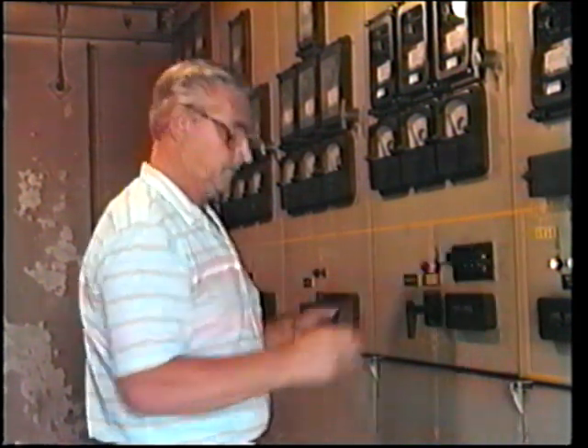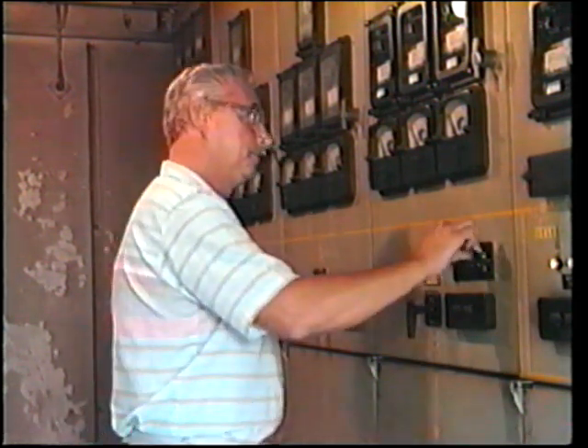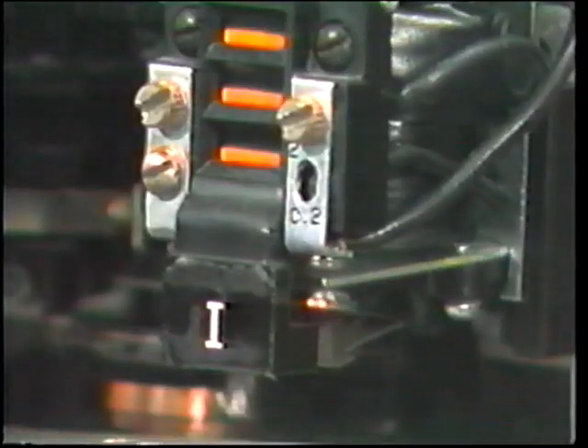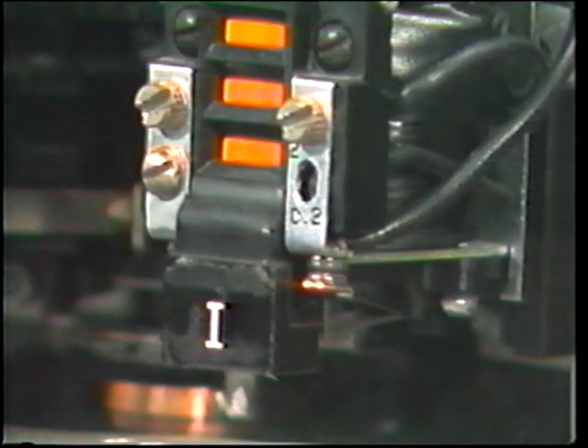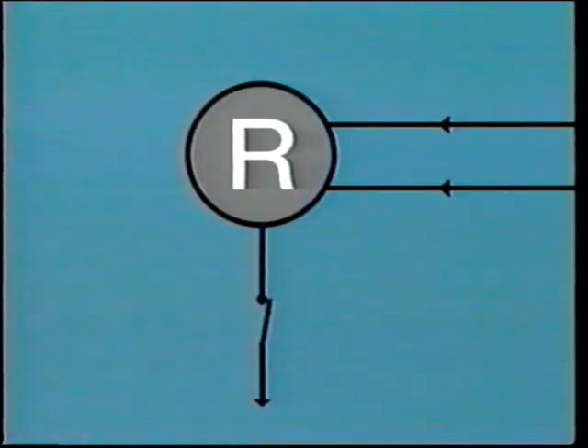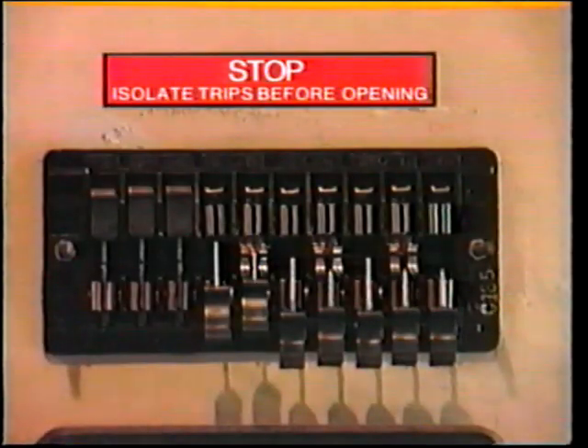He then, by mistake, opened the wrong flexi-test switch. This caused an unbalanced condition in the relay, which consequently operated and tripped the breakers. The main problem here is that they had failed to isolate the trip circuits from the relay before commencing the test. In fact, it is usually established relay test practice to isolate trip circuits as soon as the relay cover is removed. Moreover, this particular relay has a red warning sign placed directly over the flexi-test switch. It says, "Stop. Isolate trips before opening." In spite of this, the technician went ahead and caused the inadvertent trip.